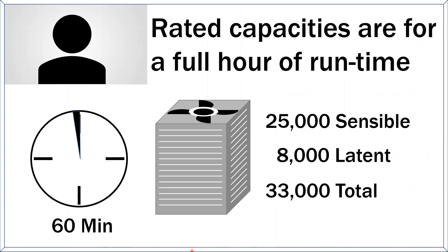But when you do look at the actual performance of the system, and you have your sensible and latent loads broken out, that's for a full hour of runtime. That's the unit kicking on, running, and then kicking off. Well, in a partial run cycle that doesn't run for the full hour, what do you suppose our sensible and latent total numbers are going to be? 12,000, 25,000, 8,000, 33,000. We'd expect what, 12,500, 4,000, whatever half of 33,000 is. I'm not going to math them. Was that 16,500, I guess? All right, once again, brazenly fabricated data here, made up.